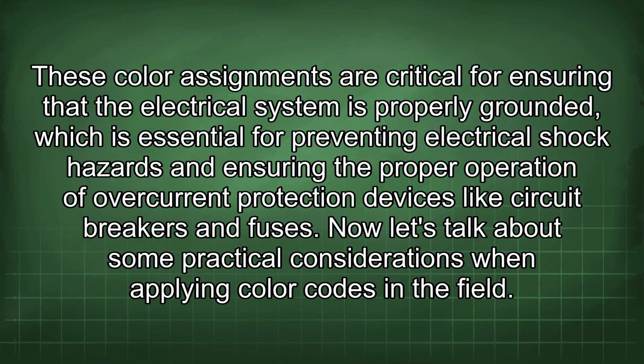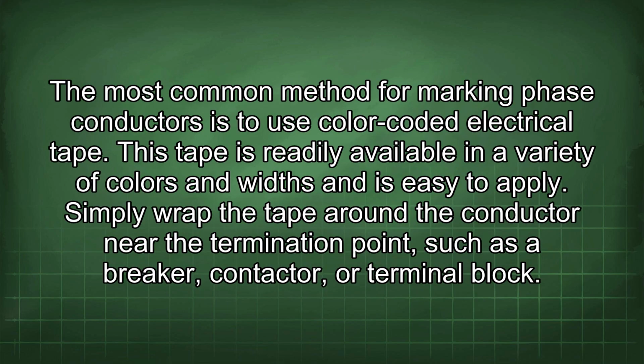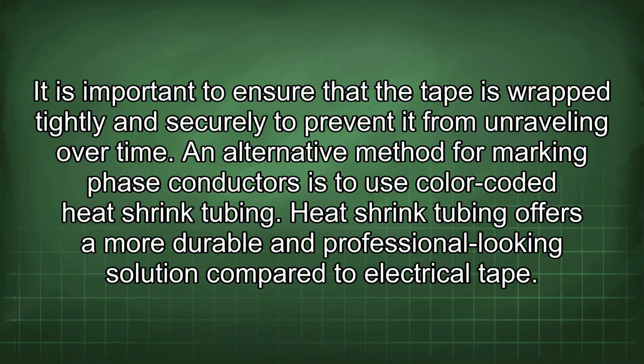Now let's talk about some practical considerations when applying color codes in the field. The most common method for marking phase conductors is to use color-coded electrical tape. This tape is readily available in a variety of colors and widths and is easy to apply. Simply wrap the tape around the conductor near the termination point, such as a breaker, contactor, or terminal block. It is important to ensure that the tape is wrapped tightly and securely to prevent it from unraveling over time.